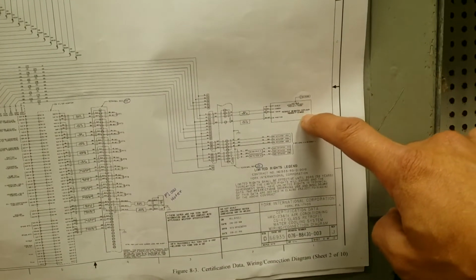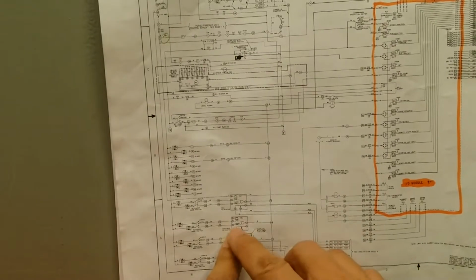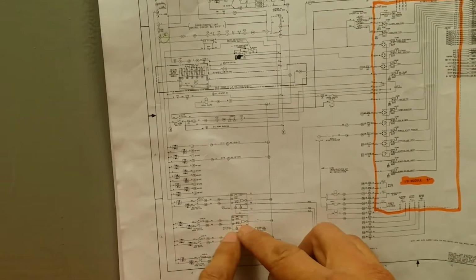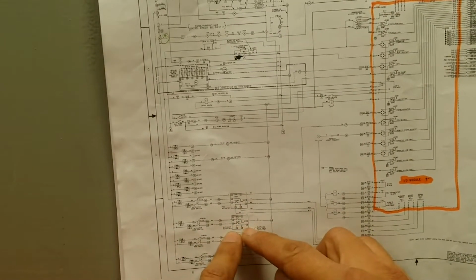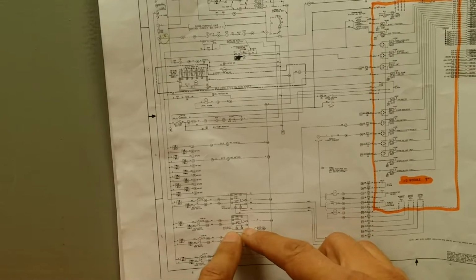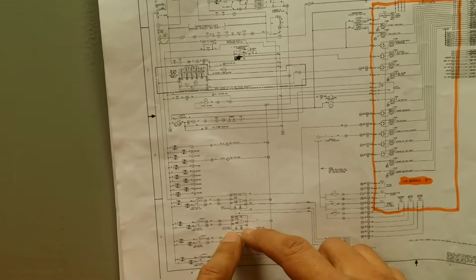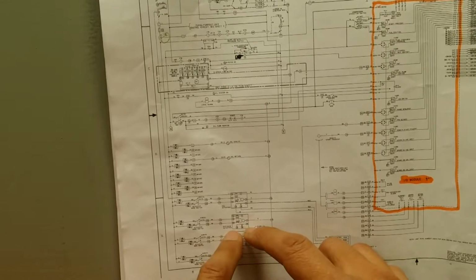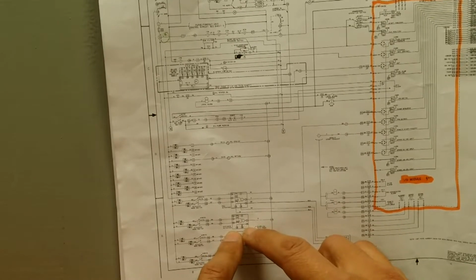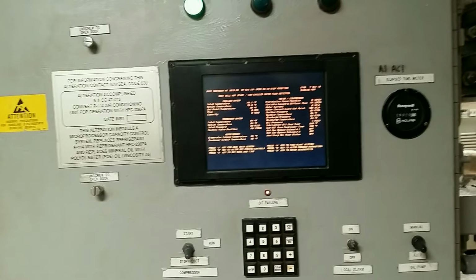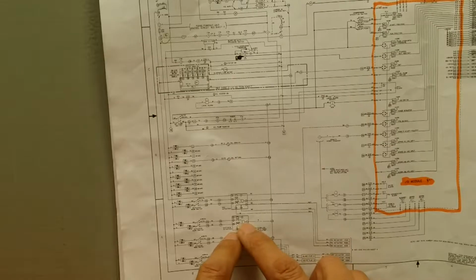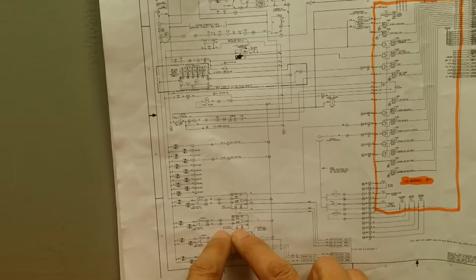So this proximity sensor detects the diffuser distance. I was told by the field technician that one caution for the diffuser is that you cannot go with righty tighty, lefty loosey. He says that sometimes righty means open the diffuser, sometimes righty means close the diffuser. What you do is have somebody out there open it, and then you look at the display and see if the percentage is increasing or decreasing, and that's how you can tell before you start calibrating this. So that is the diffuser actuator.